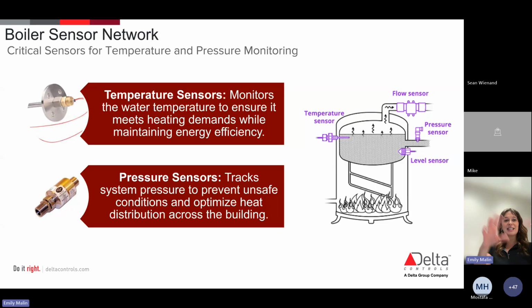Within our boiler system, we're going to have a bunch of sensors as well. I put this before our schematic because I want you guys to try and focus in on what's going to be our inputs, what's going to be our outputs, what we're really starting to track, and what we're needing to track, right? So in this scenario, we're going to have temperature sensors, whether those are on the boiler themselves or inside of the zones. Basically what we're doing here is monitoring the temperature of that water to meet the heating demands, while maintaining efficiency in our energy, right? We don't want this to just be cranking up and up and up, and we don't need it to be doing that. Pressure sensors, I know Moose brought up safety and pressure sensors. This is going to be a big deal in boilers because we do want to prevent unsafe conditions. Nobody wants to blow up a boiler. So again, you're just going to have all of these sensors along the way when we start to think about what we are controlling. A lot of this is in play when we think about our boiler system network in general.